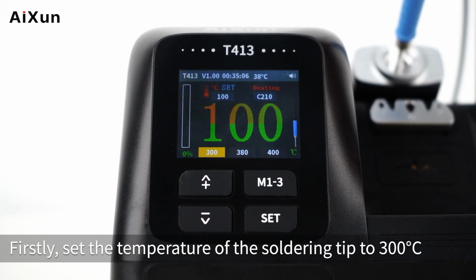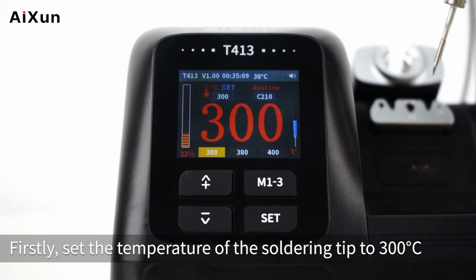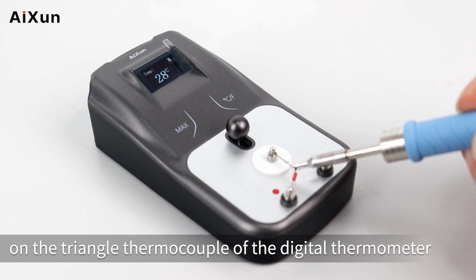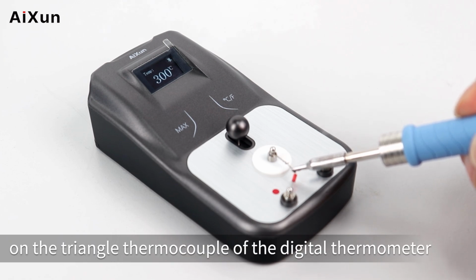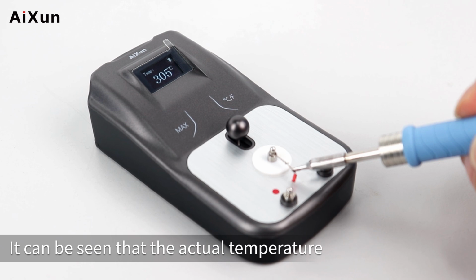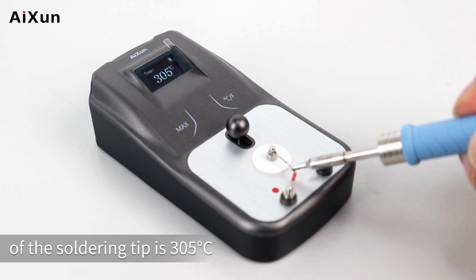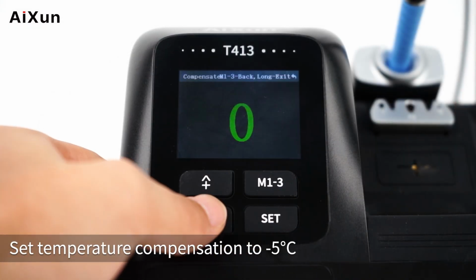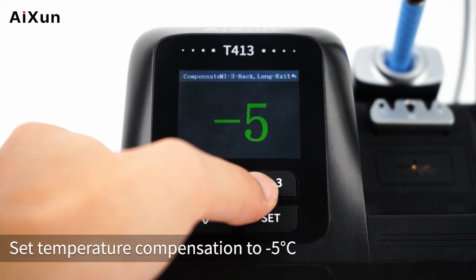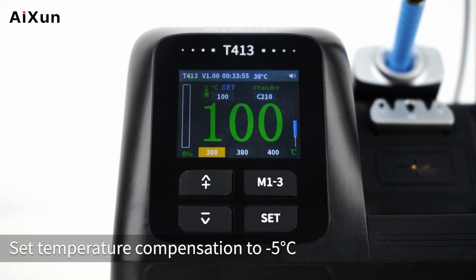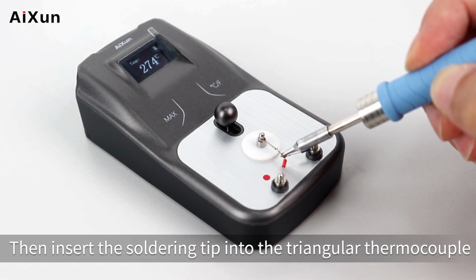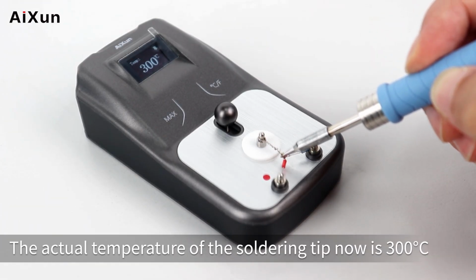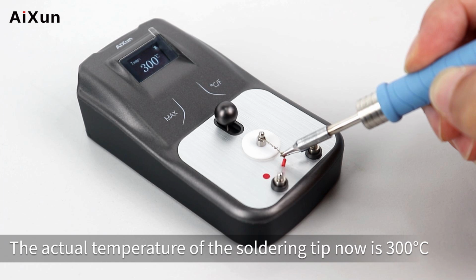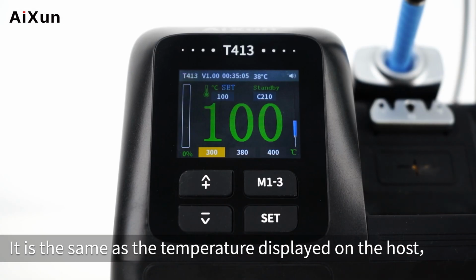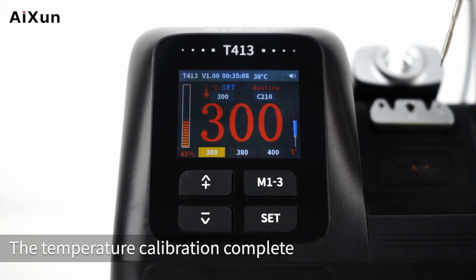Firstly, set the temperature of the soldering tip to 300 degrees Celsius. Place the soldering tip on the triangle thermocouple of the digital thermometer. It can be seen that the actual temperature of the soldering tip is 305 degrees Celsius. Set temperature compensation to -5 degrees Celsius. Insert the soldering tip into the triangular thermocouple. The actual temperature of the soldering tip now is 300 degrees Celsius. It is the same as the temperature displayed on the host. The temperature calibration is complete.